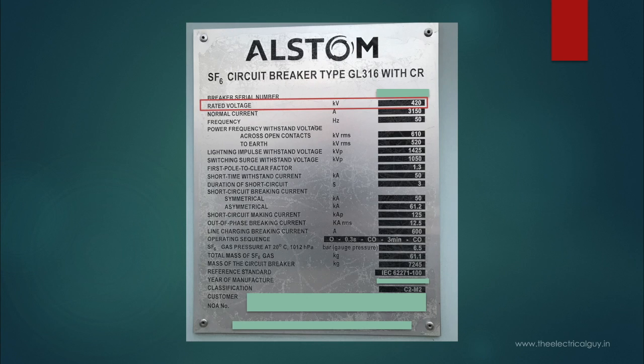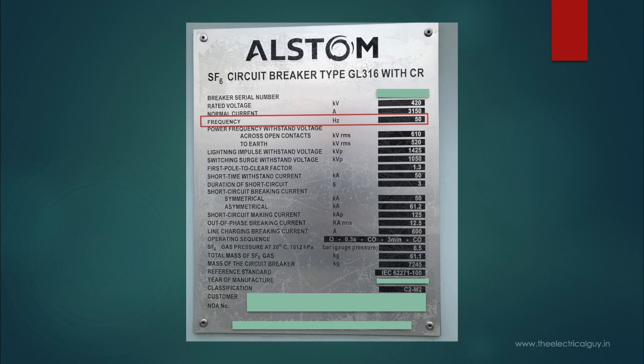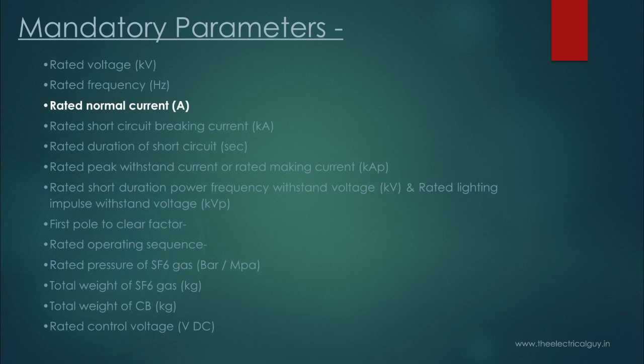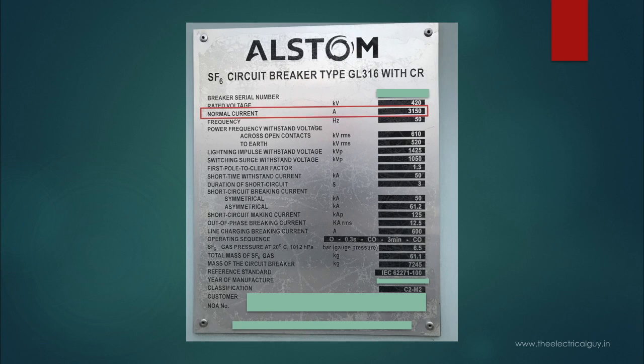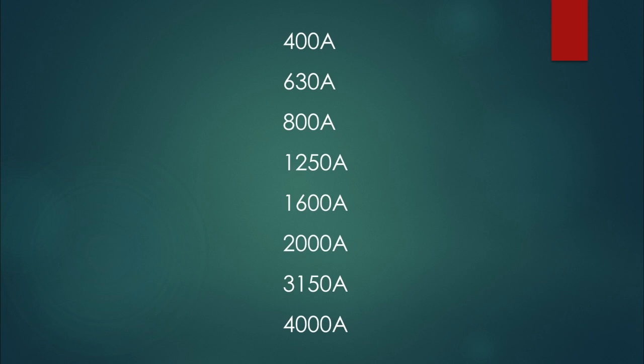Similarly, for the 245 kV voltage level, rated voltage is 245 kV and normal voltage is 132 kV. Rated frequency is the power frequency on which electricity is generated, transmitted, and distributed — in some countries it is 50 Hz and in some it is 60 Hz. Rated normal current is the RMS value of rated current which the circuit breaker can carry continuously. It is given in ampere, and there are preferred values of rated current.